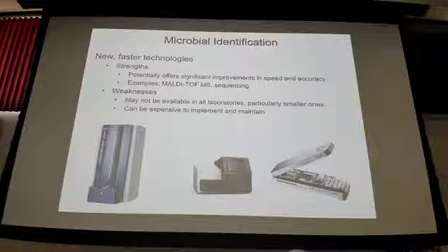So you put your little bacterial isolate, your pure colony, associated with some matrix, some analyte, on a little stainless steel dish and load it onto that instrument at the bottom here. Once you load it into that specimen port, a laser zaps that specimen, basically ionizes it, it desorbs, and it gets shuttled through this entire vacuum tube right here. That's the time of flight portion of it.